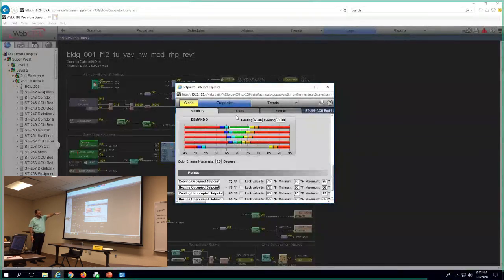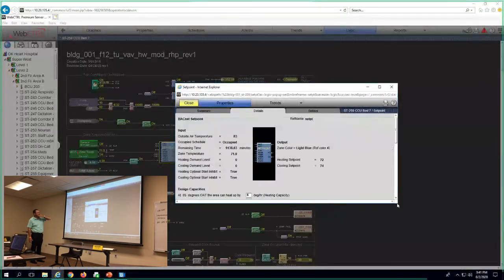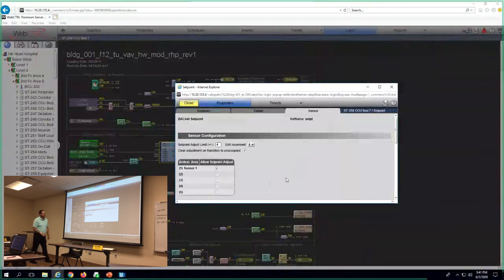All right, so go to details, Joe. Scroll down, scroll down. So that's the design parameters we put in for design degree days. It has to do with optimal start-stop. So if we were using optimal start-stop, which again, we're not doing here, click on sensor right here. See that set point adjust limit? You can change it right there. So for each zone, if you go into this blue block in the logic, and if you wanted to make it 12, whatever, you click on it, and you can run that thermostat up and down as much as you want to allow.